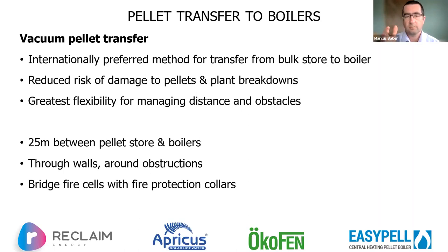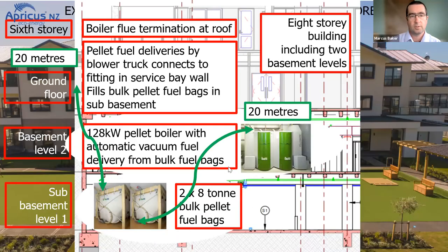So there really shouldn't be any reason that we can't get between A to B. And we'll just look at how we can go beyond 25 meters at some point going forward. But just to recap, and we saw this slide before, this is the design that we saw a minute ago from NDY, where we've got two 8-tonne stores in the sub-basement one, and then about 20 meters away is the 128-kilowatt boiler in the plant room, and then flowing up.